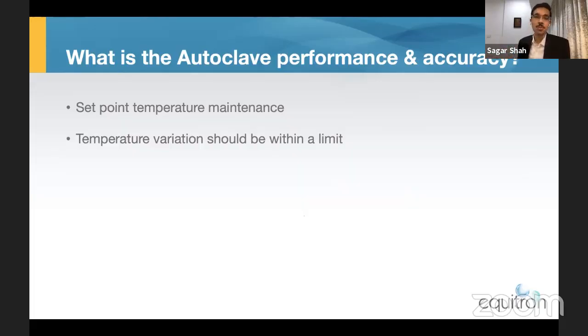If the sterilization set point is 121, and if the autoclave temperature reaches 125 or 126 degrees Celsius, then it is overheating your load, and it might even cause damage to sensitive loads like media. So unless you're using the autoclave for discard or just straightforward sterilization of glassware, temperatures of 125 or 126 degrees Celsius will in fact be detrimental to your loads.